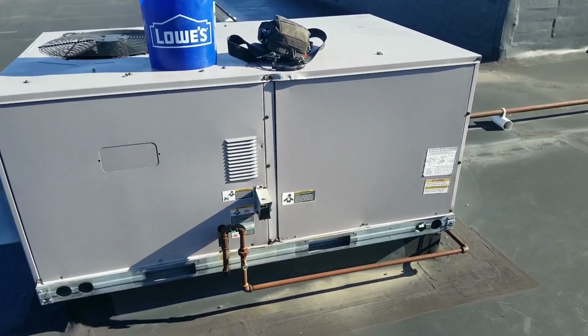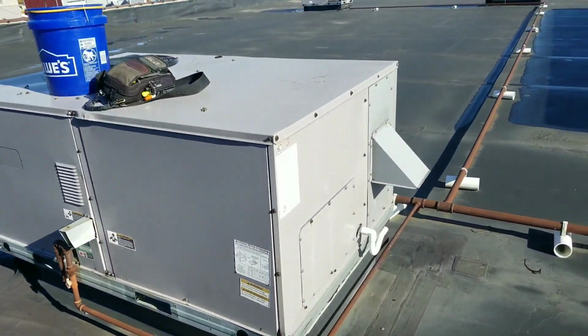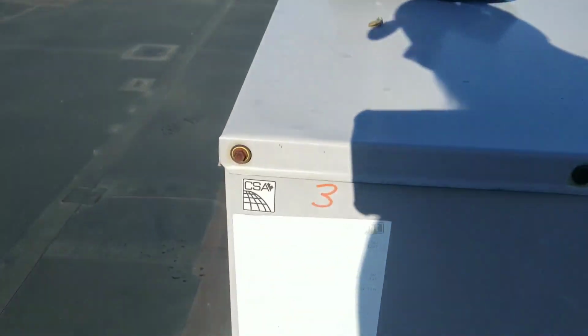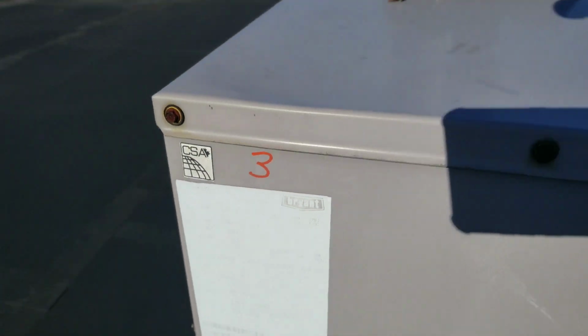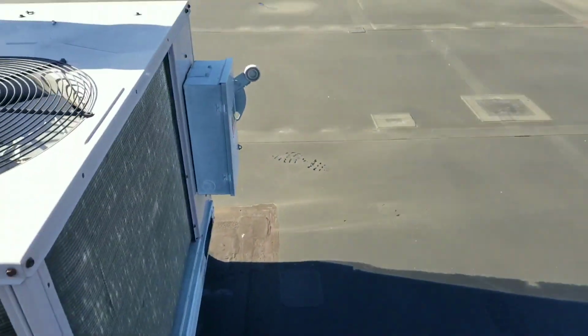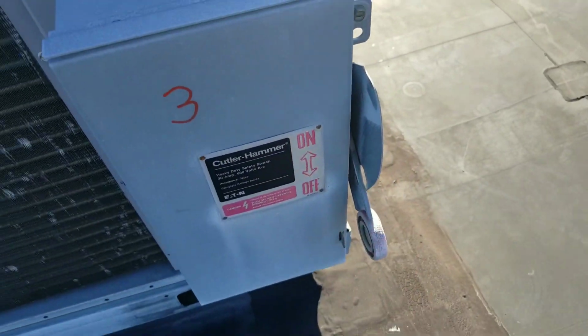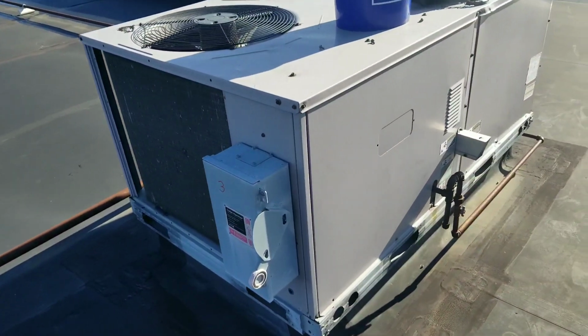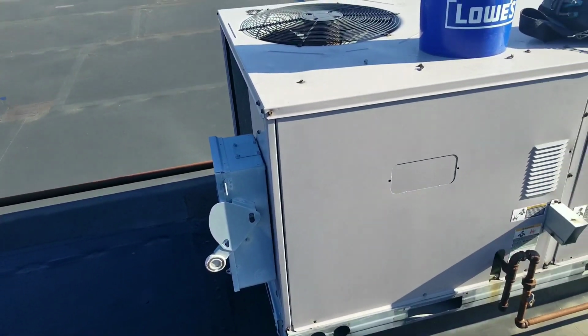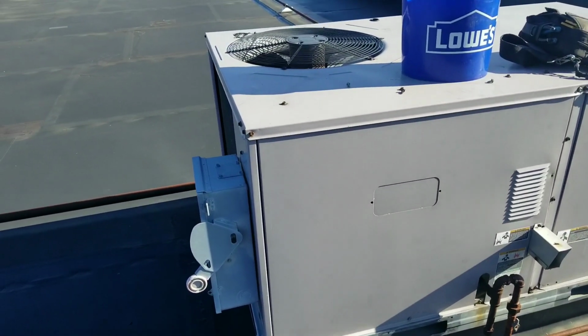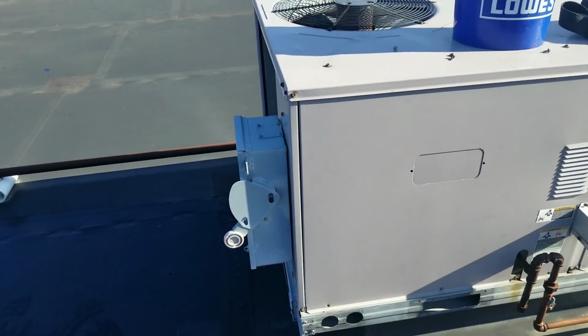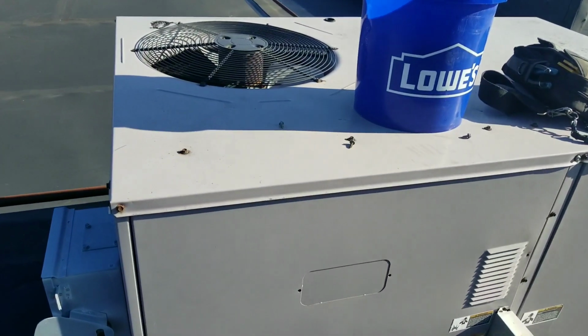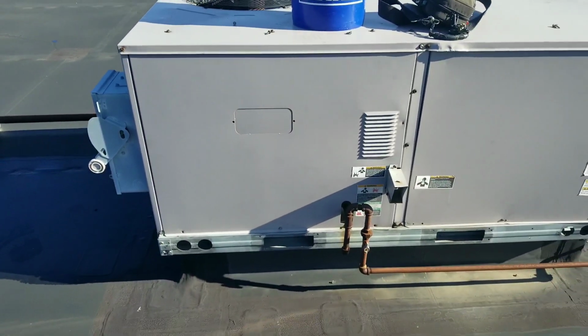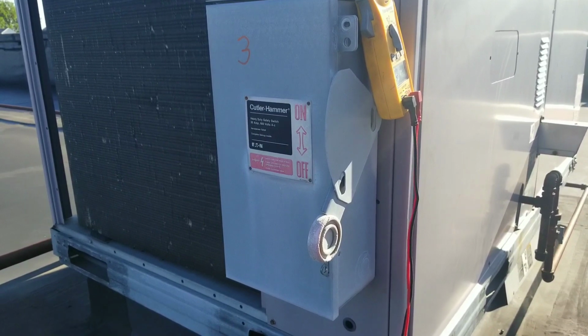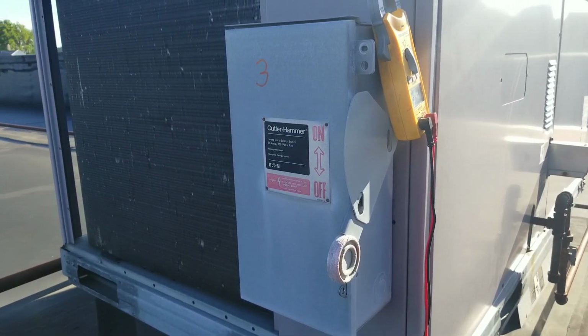Here we are at the roof. This is our unit that is not working. Kind of see the model and serial number on it. So like I said, before I go down and reset that breaker, I'm going to shut this disconnect off. This way I can flip that breaker and I'll have power at this disconnect. I can come up here and troubleshoot, and if need be, if I find the problem and it's an easy fix, I can just turn my disconnect back on and be all set. Alright, my disconnect is off. The breaker downstairs has been reset.